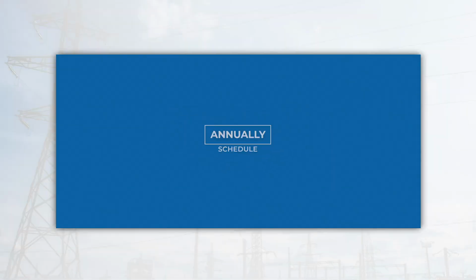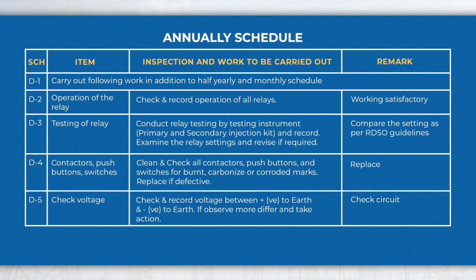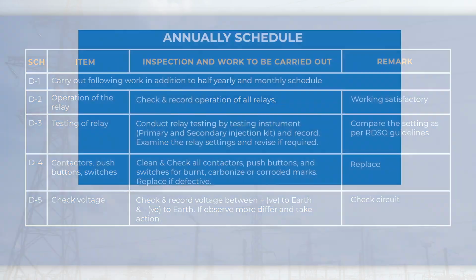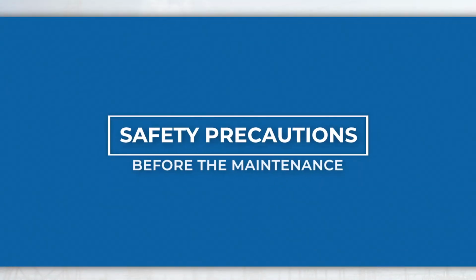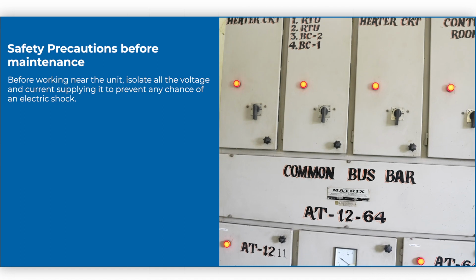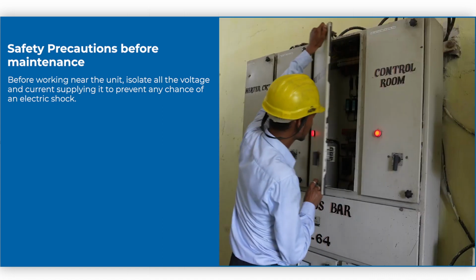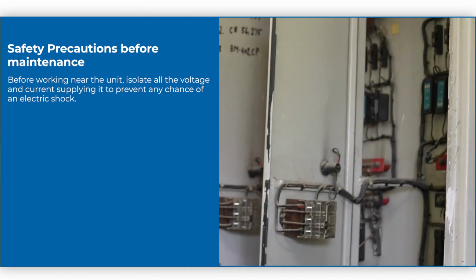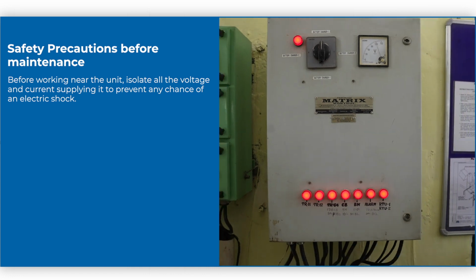Annual schedule. In an annual schedule, perform activities like check the relay operation, do the relay testing, check contacts, push buttons and switches, check the voltage between positive to earth and negative to earth, etc. in addition to half-yearly and monthly schedule activities. Safety precautions before maintenance. Before working near the unit, isolate all the voltage and current supplying it to prevent any chance of an electric shock.